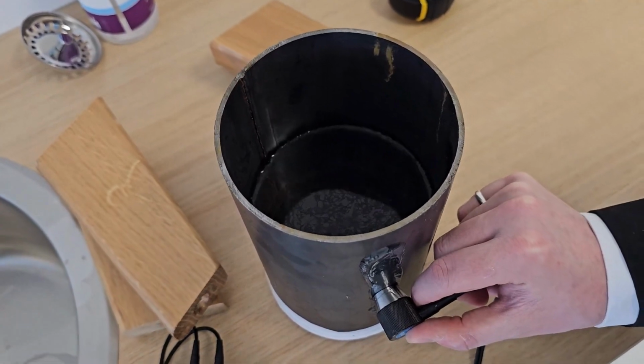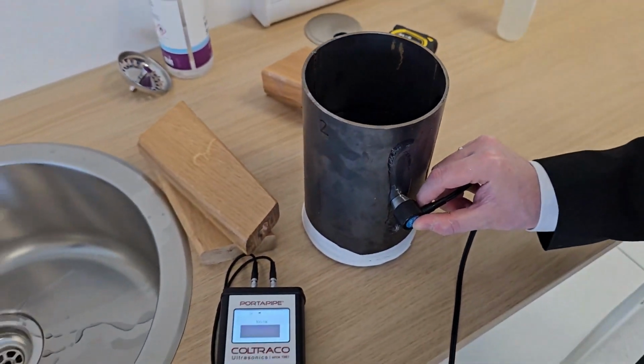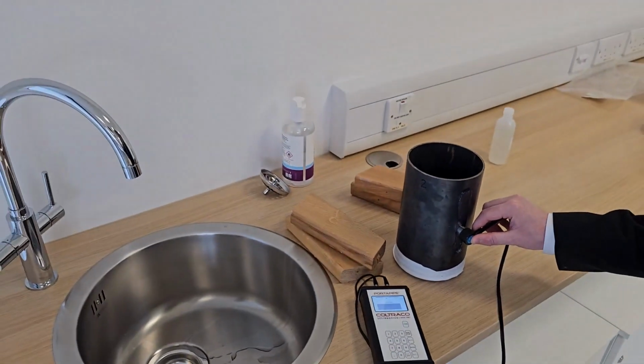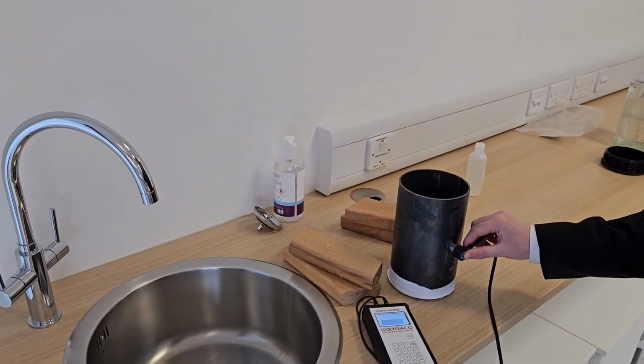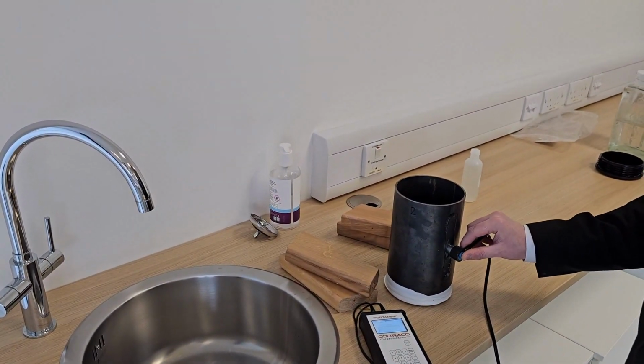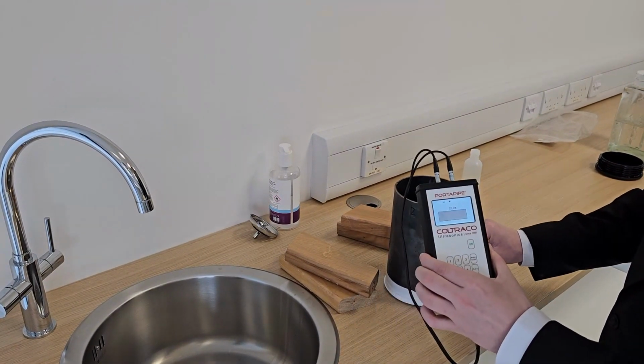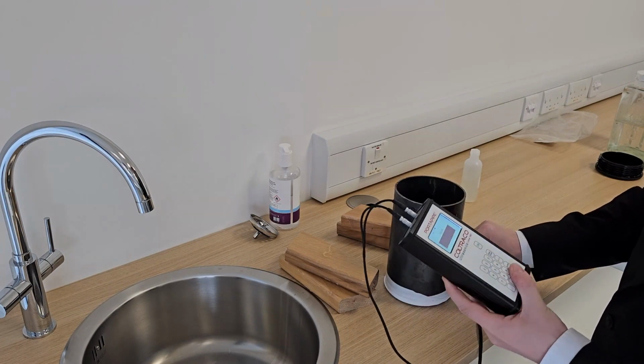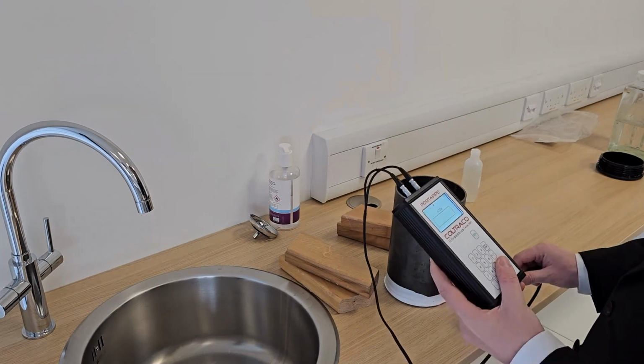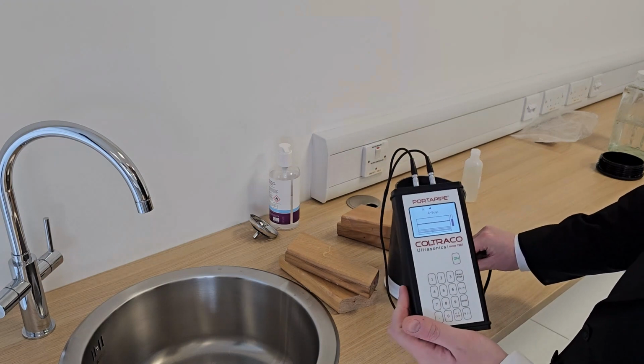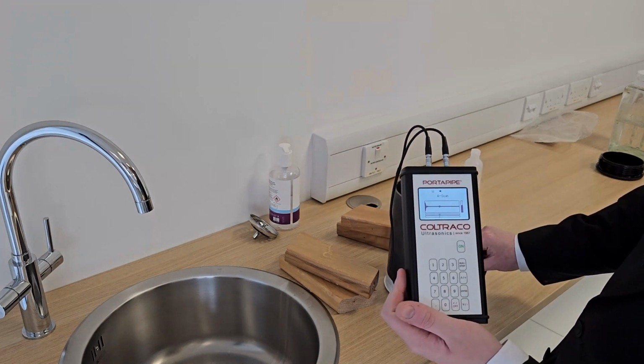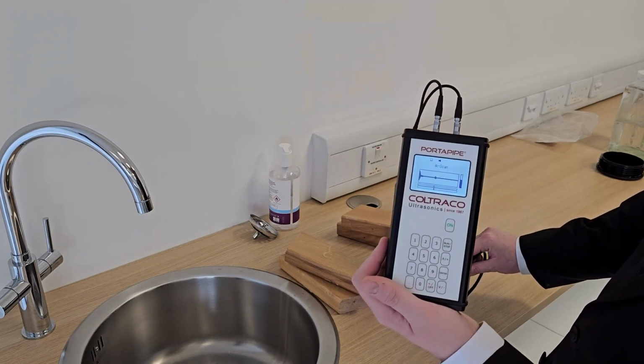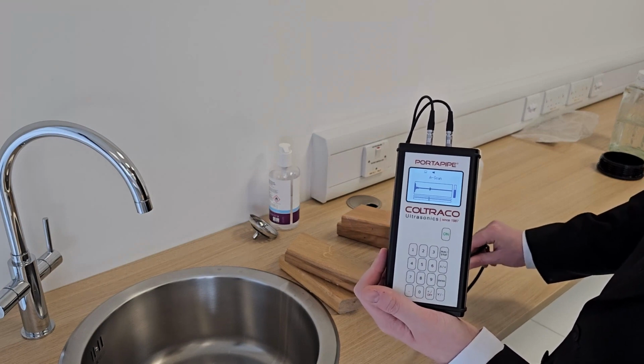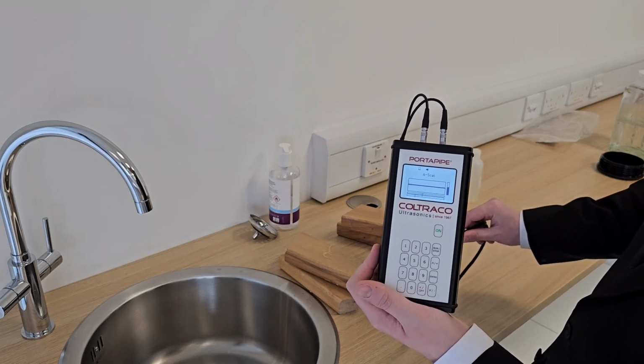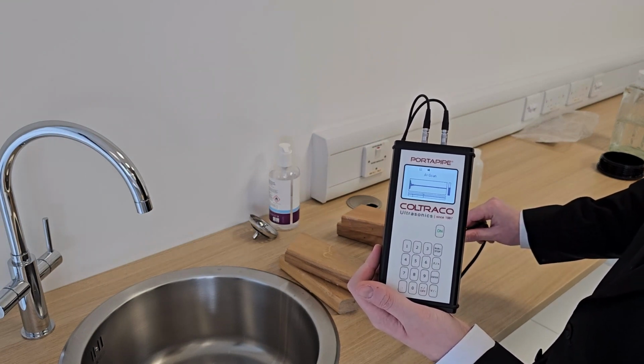I'm not sure how clear that is, but just as before, the sensor has just dipped below the liquid level, and our readings change from random to full. And I'll just again show you the A scan on that so you can be completely clear. Here you see we have a reflection there within our expected window, and above we have no such reflection.